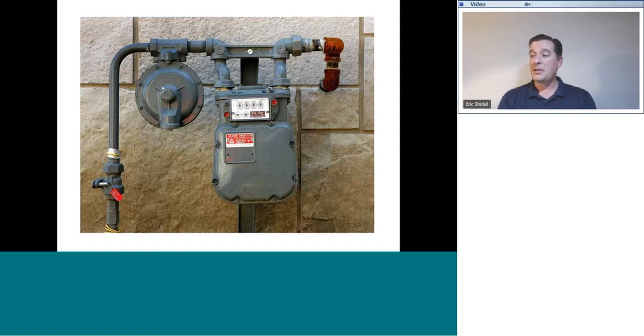As an experienced gas heating tech, someday you may say to yourself, I can adjust a gas regulator. That's true, as long as it's owned by the customer. If it's owned by the utility provider, leave it alone. Ask them to please come and adjust it, and they will probably be more than happy to do so. All regulators have a vent. All regulators will produce a constant outlet pressure that is a certain amount higher than the atmospheric pressure.